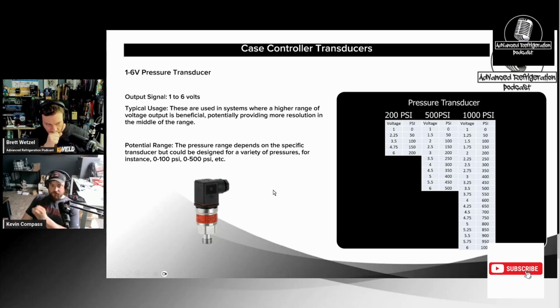Power out is going to be your signal input. So what you're going to do is find all 3 of these wires on the board. And I always start like this. I go from the power feeding the transducer, meaning your 5 or 12 volts, and I will go to ground on the board. The sensor or transducer ground, meaning the signal ground, I will go there and check my voltage.